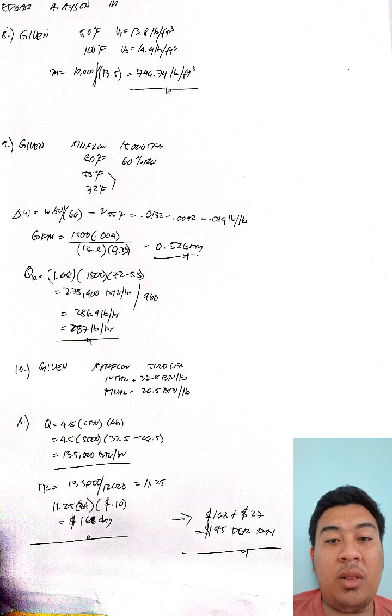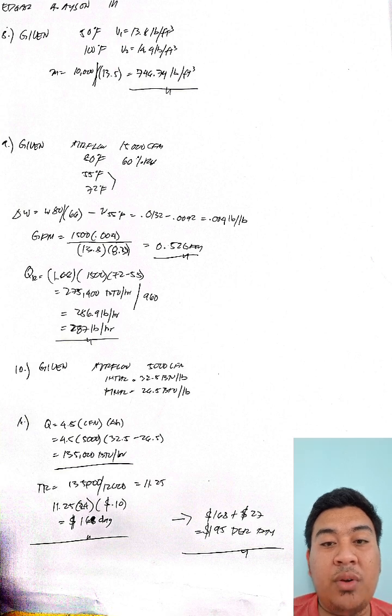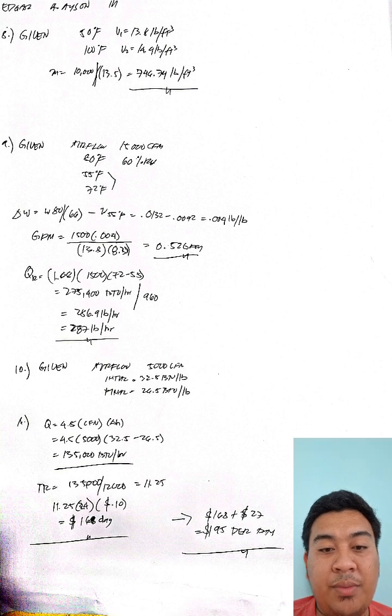Then for the reheat load, with a given constant formula, 1.08 times CFM times delta T. So by substituting all the values, 1.08 times 15,000 times 72 minus 55 for the delta T, then I got the answer of 275,400 BTU per hour. Then divide it by 960, then I got the answer of 286.9 pounds per hour of steam, which is 287 pounds per hour.